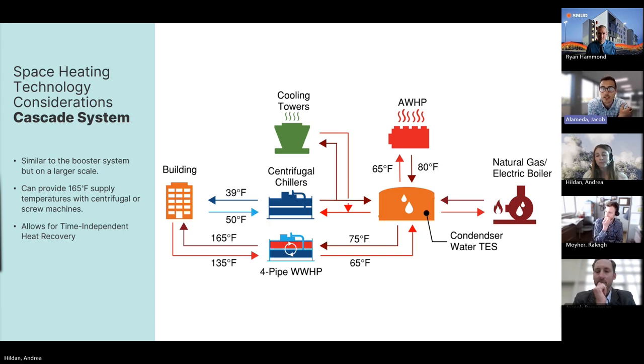In the natural gas or electric boiler, you can use either or. One of the limiting factors is obviously electricity. It has to be coming into your building from somewhere. So say you're already tapped out of your electrical capacity and you approach SMUD, and it would be a big project to add the electrical infrastructure that would price the project out, and they wouldn't do any of this electrification because of that limiting cost factor. Then maybe just using a natural gas boiler on that piece makes sense. Maybe that saves cost of the electrical infrastructure upgrades. Maybe they don't have enough room to put those air-to-water heat pumps. Maybe you're on a restricted site and you just don't have the land available, the space. We run into that all the time, especially in downtown facilities where you're just out of space for air-to-water heat pumps because they are big and loud. You could use the electric boiler, but then does that put you past your electric capacity at your building?